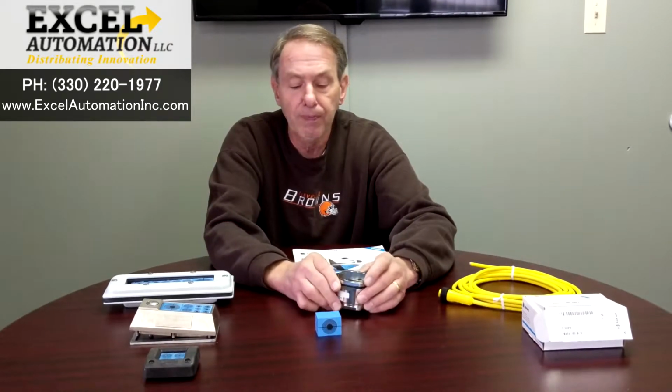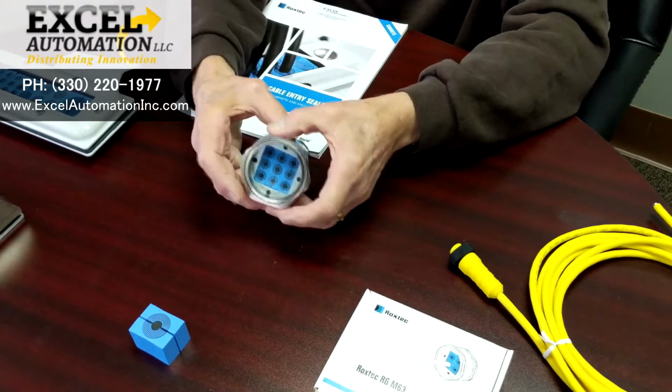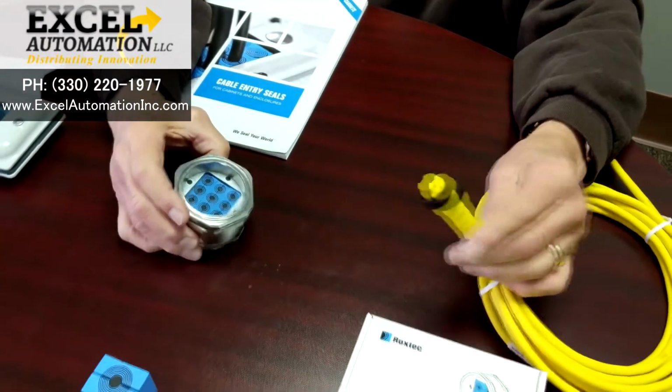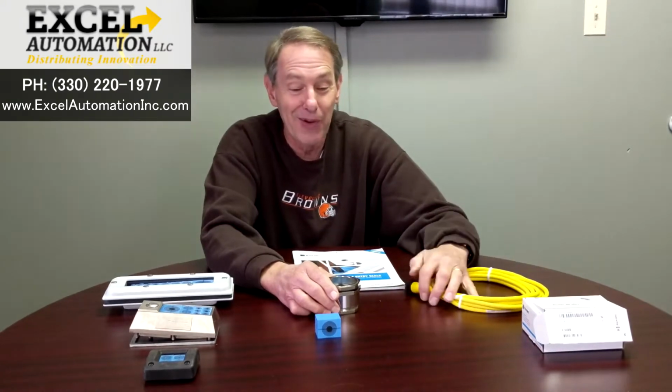electrical enclosure. The product, by its design, then can accept pre-terminated cables, as long as the terminal or the connector on the end of the cable will pass through the opening in the frame. No need to cut off the connector, just remove the modules, pass the cable through, and then restore the modules. Nobody wants to solder a connector on the end of any cable. That's a lot of work and a lot of risk.